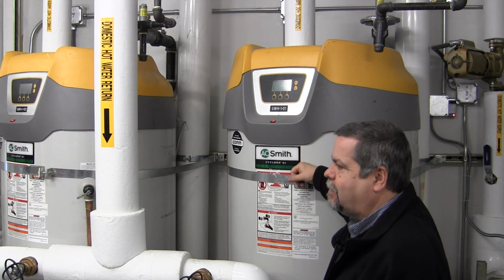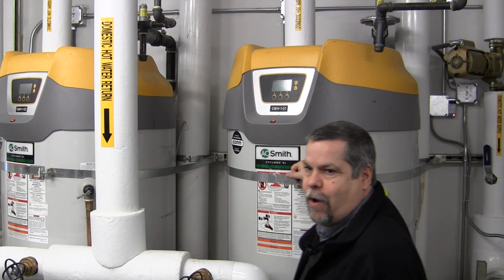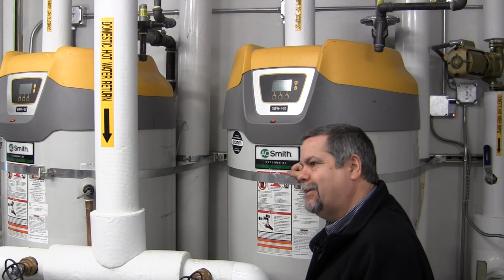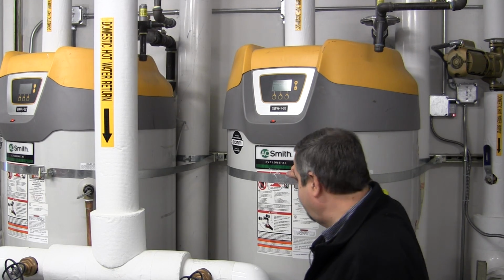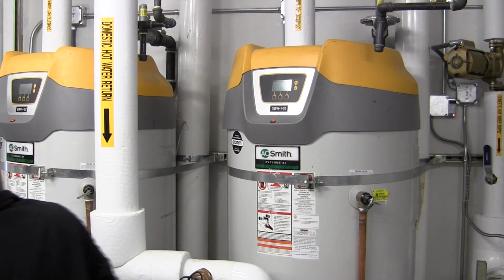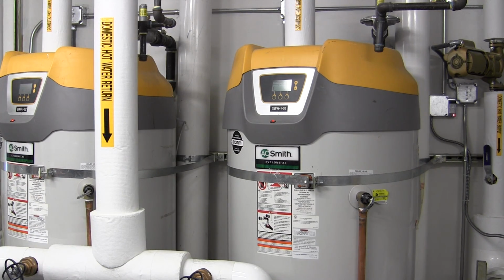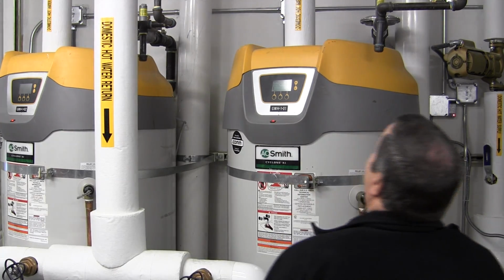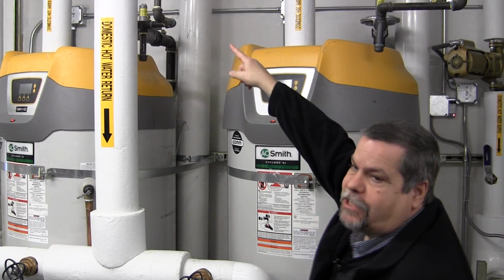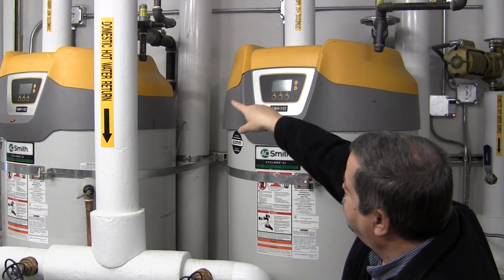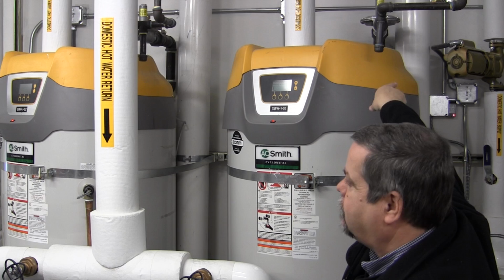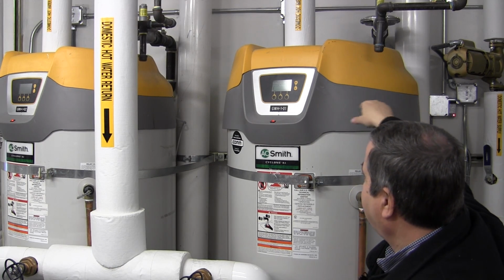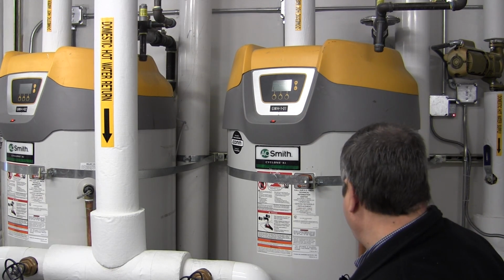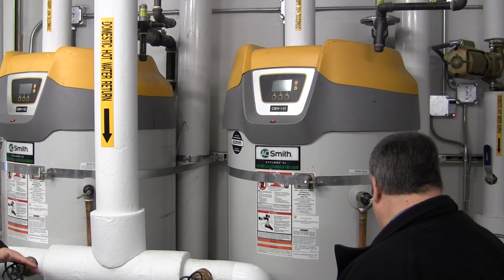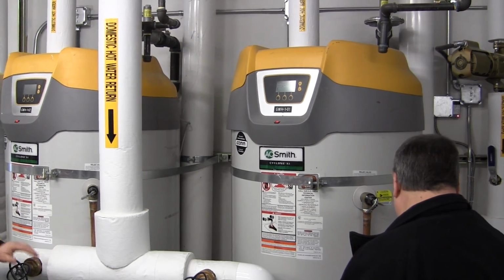This strapping is probably your seismic requirement in case a giant earthquake hits Eugene. We don't want them to fall. Gas shutoff valve would be right there. Your gas shutoff valve, and probably those are emergency shutoffs up there. Shut the electricity off the unit, or those are the disconnects for the units. Okay. And then you have, per boiler code, your gate valves in and out.